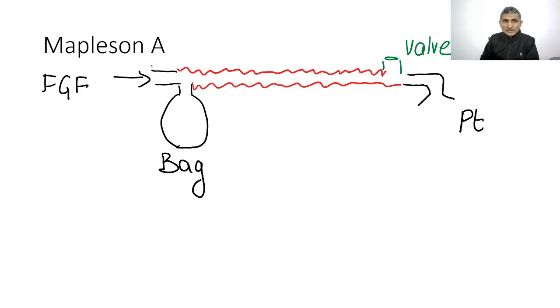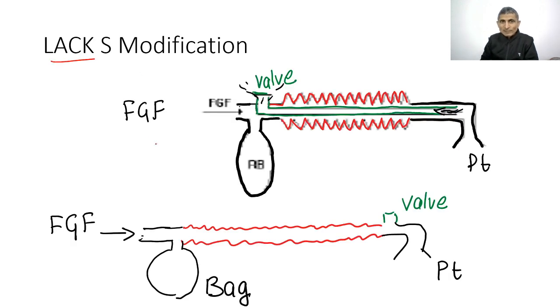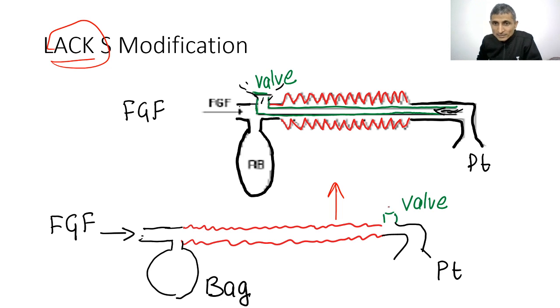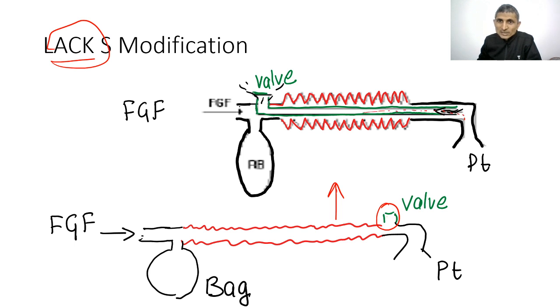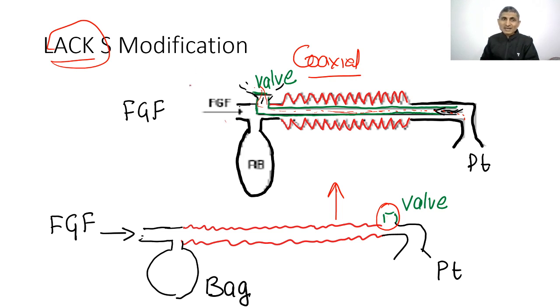The Mapleson A (Magill circuit) has fresh gas flow from one end with a valve toward the patient. The Lack circuit is a modification of Mapleson A — the valve is shifted to the machine end and expiratory gases vent through an inner pipe (tube within tube), making it a coaxial circuit. The Lack circuit is a modification of Mapleson A.